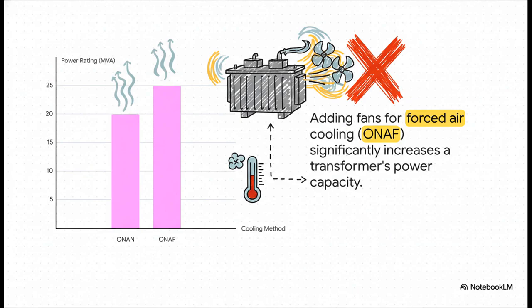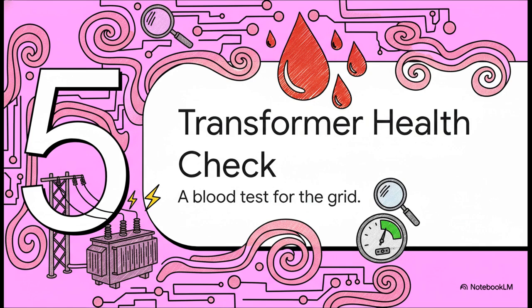The bar on the left, ONAN, is the transformer's power rating with just natural air cooling. It's rated for 20 megavolt amps. Now look what happens when you just add fans for forced air cooling, ONAF. Boom! Its capacity jumps to 25 MVA. This means if those fans fail, the transformer's capacity instantly drops by 20%, and if it's already heavily loaded, it's going to start to overheat, and fast. Which brings us to our final section.